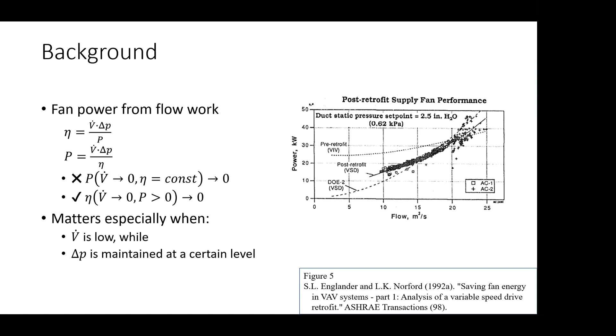In a typical simulation program, we often simplify the functional dependency of power on both flow rate and pressure to just a dependency on flow rate, usually because it's difficult to compute power in simulation programs — it tends to form algebraic loops. For example, in ASHRAE Standard 90.1, there's a curve that uses the power ratio to express this functional dependency of power over flow rate directly. It doesn't exactly cross zero, but it's essentially zero if you look at the formula closely.